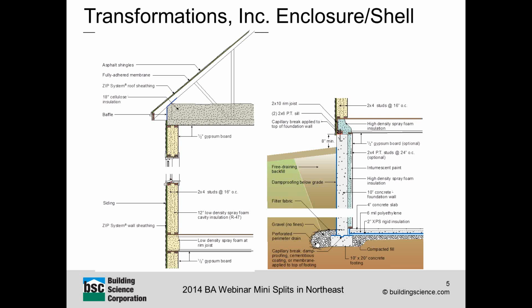In this study, we used equipment from Mitsubishi. There are a couple of other manufacturers that have some fantastic low temperature performance, which is critical if we're talking about relying on these heat pumps as the sole source of heating in a cold climate like Zone 5, Massachusetts. So they retain their full heating capacity at an outdoor temperature of -5 degrees. They're rated down to -13, and some other practitioners that I've met have had them operating down to -20. And note this is a specific type of equipment from a certain manufacturer. Other manufacturers do have equipment that can run down to this level.